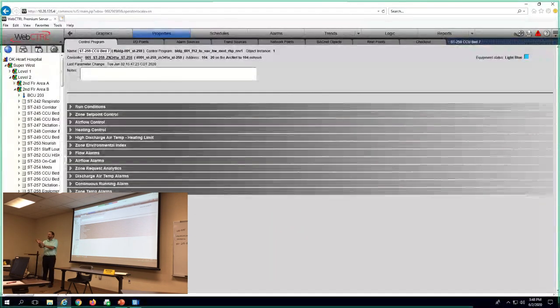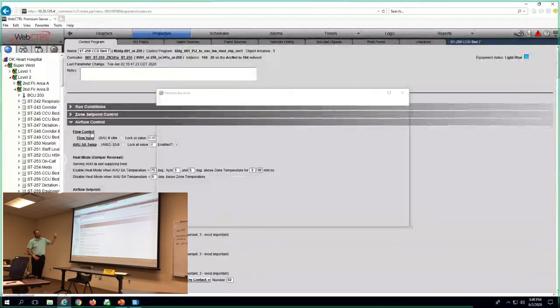Just out of curiosity, how often does this happen, the parameter download required up top left? It's on my screen. I think it's because you're messing with the same one, or a different one. Maybe Joe was double clicking and he got overzealous. Just go ahead and hit download. You're not going to hurt anything. Hit download, because the overall database has a mirror image of what's out there in every controller. If you change something and apply a change, and it's already sent something to the controller, the database says, okay, we got another update with a different timestamp, and it needs to be downloaded again. So if you click twice real quick, it queues up. Just hit download, get it cleared up.